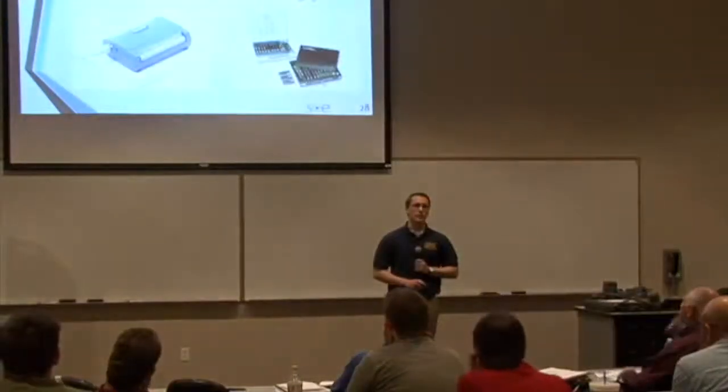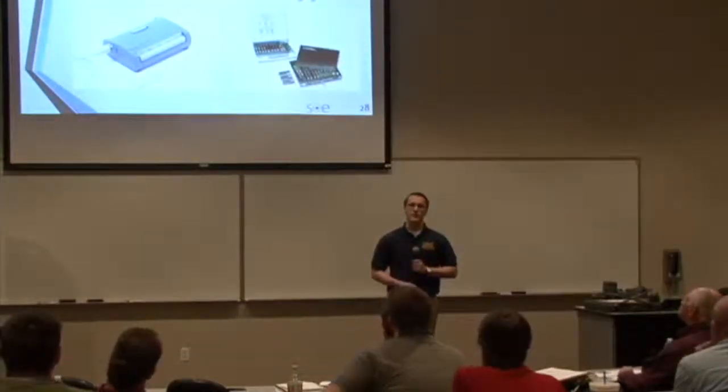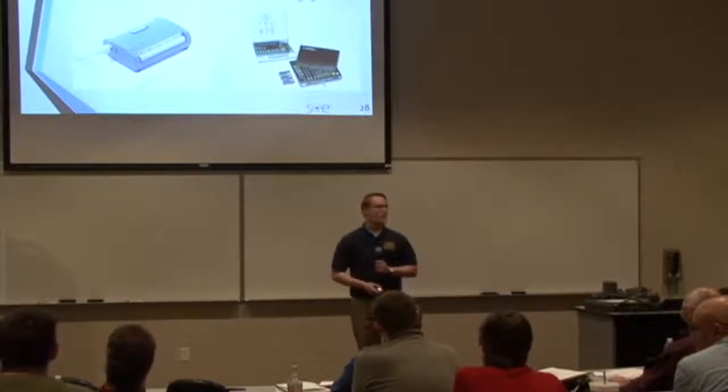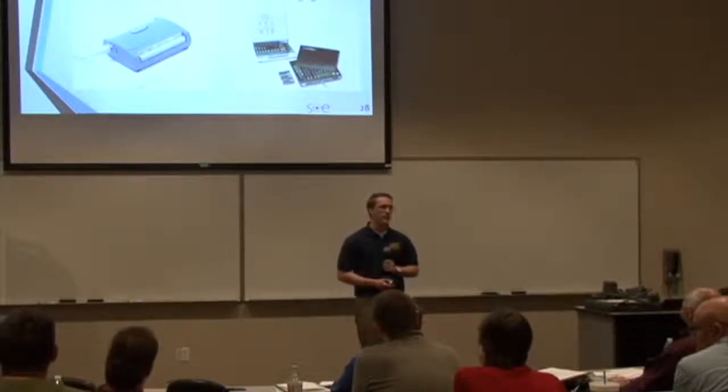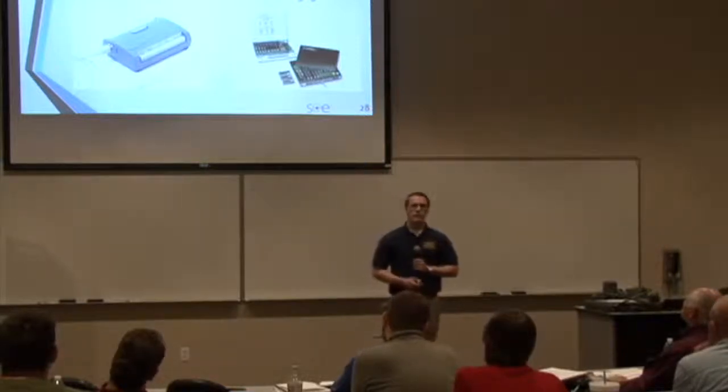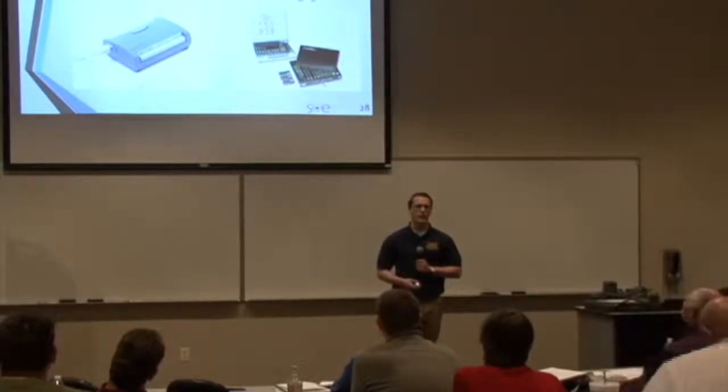That being said, one of the primary differences between our instrumentation scheme and the one used by the original C-Team is the choice of DAQ, or data acquisition unit. The original C-Team chose to use a Measurement Computing USB-2305 DAQ. One of the benefits of this DAQ is it does use a USB interface, so you can use it with virtually any computer. However, because it's third party to the LabVIEW software we're using to display and report the data, there were some interfacing issues.